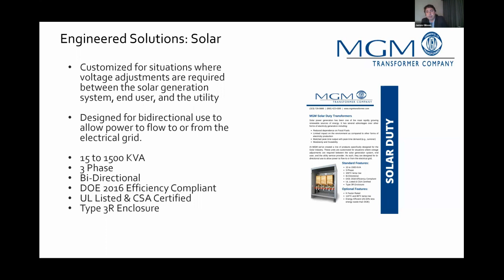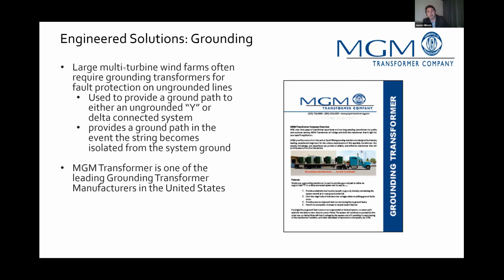Grounding transformers also for wind applications. These are basically for fault protection—if there's an ungrounded line, contractors and builders of these systems want some way to get a path to ground for their systems. We are one of the leading manufacturers of grounding transformers in the U.S. We do an awful lot of these for different organizations putting up wind farms. So there's some good alternative energy transformer applications and products that we sell.